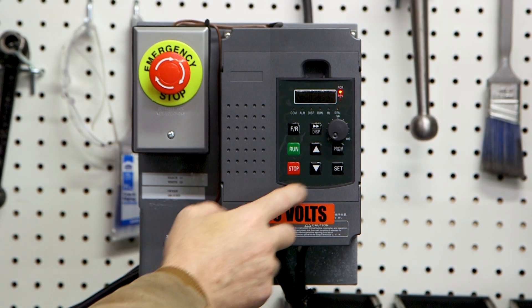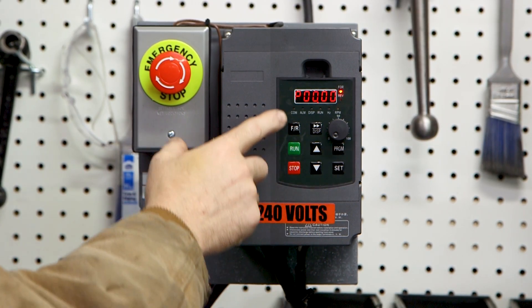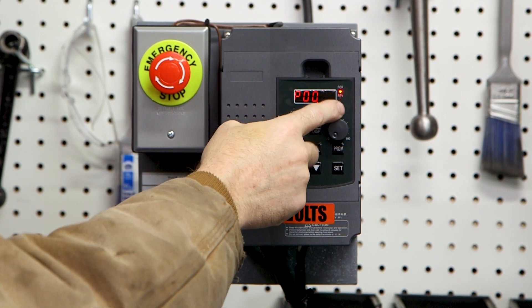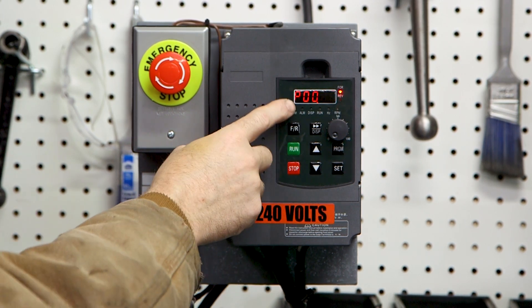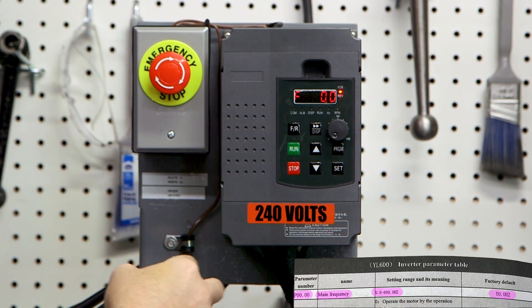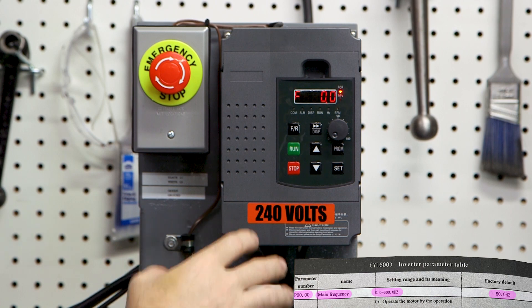So to program this VFD, we select program and we're going to get that P number I mentioned. So this is parameter 0000. And in the book, it said this was the main frequency. So this is the main frequency of our power coming in. So in the US, it's 60 hertz.